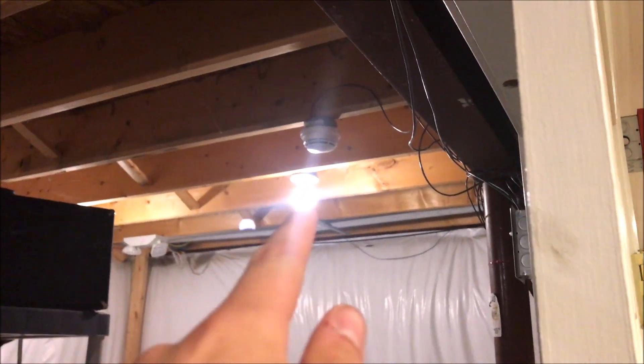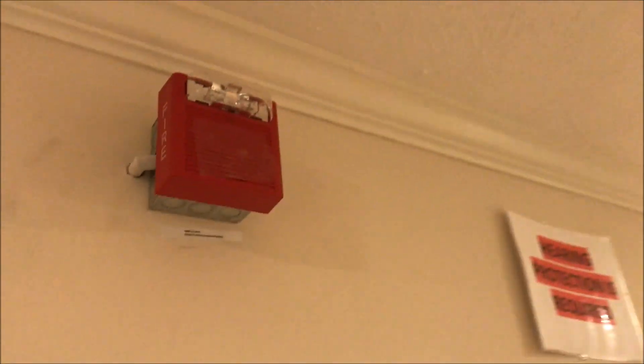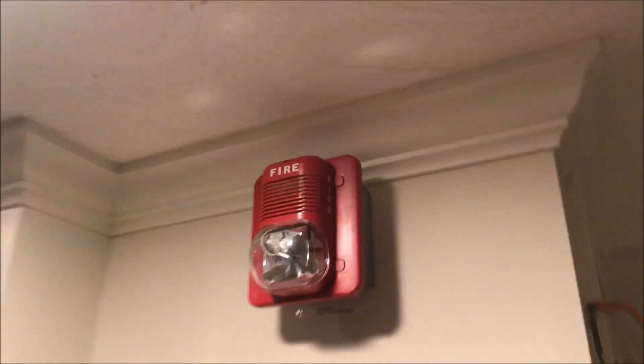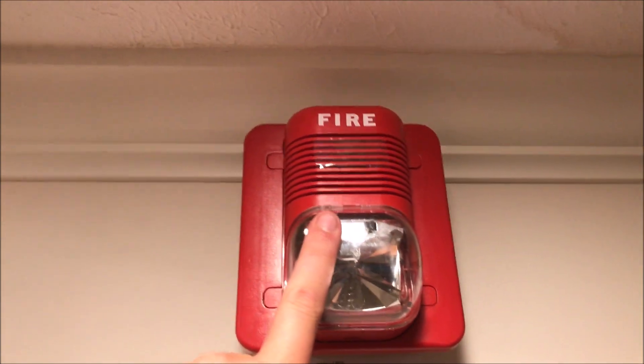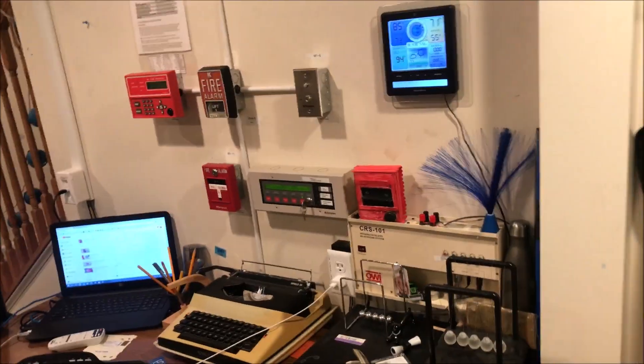Same door holder system, same smoke/heat, and we'll be solo testing that today. Same remote strobe up here. My Wheelock six-inch bell is set to continuous, and my Wheelock mechanical horn is set to Code 3, 75 candela. Then over here is my System Sensor SpectrAlert Classic 15/75 candela horn strobe, set to strobe only, and the same annunciator.